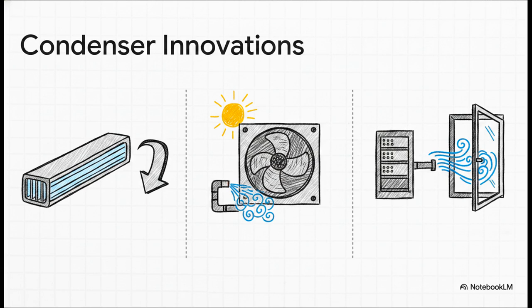Then there's adiabatic cooling, which is honestly the ultimate compromise. It runs totally waterless 90% of the year. But on those brutally hot days, it sprays a microscopic mist of water just to pre-cool the air. It basically allows the condenser to sweat like a human to cool down.